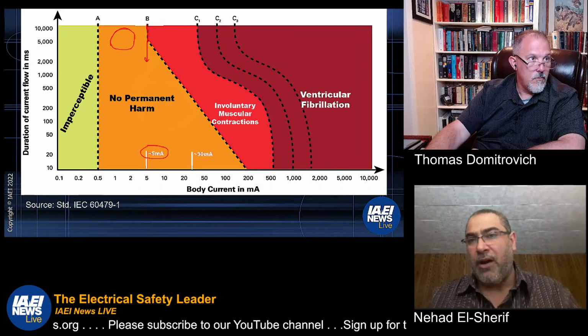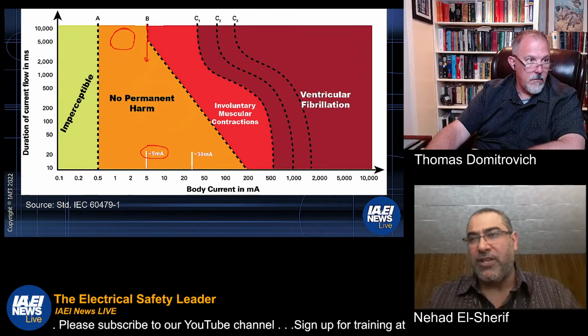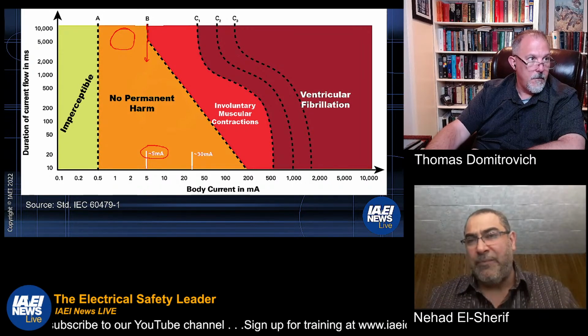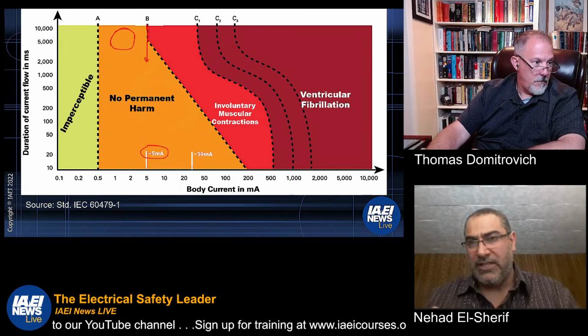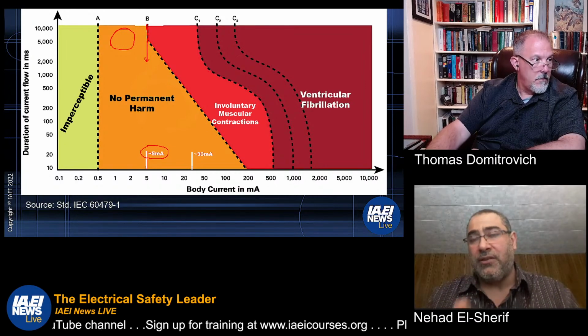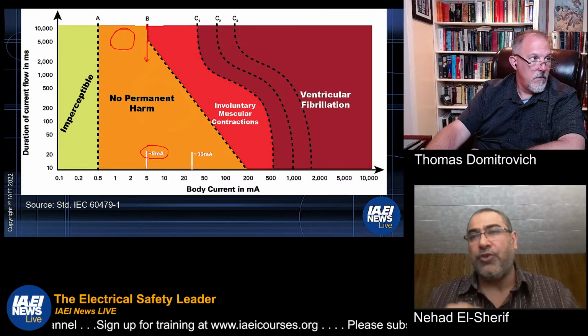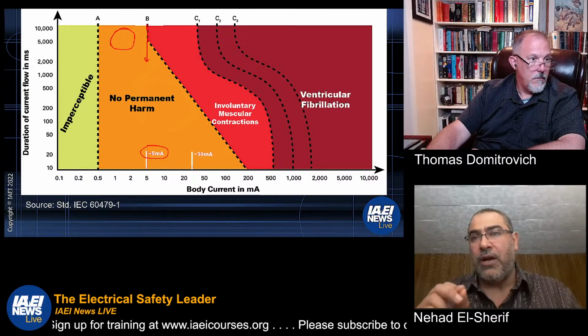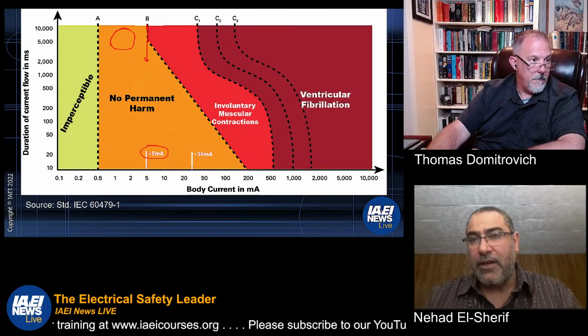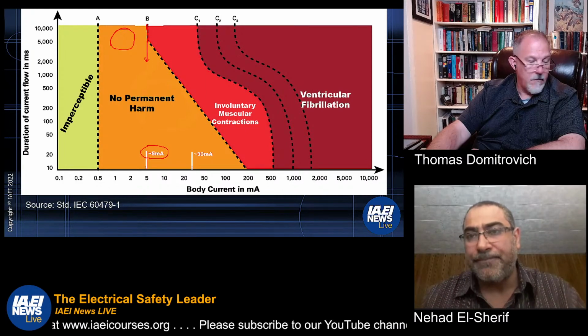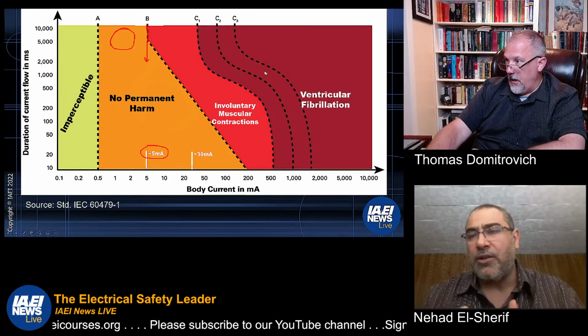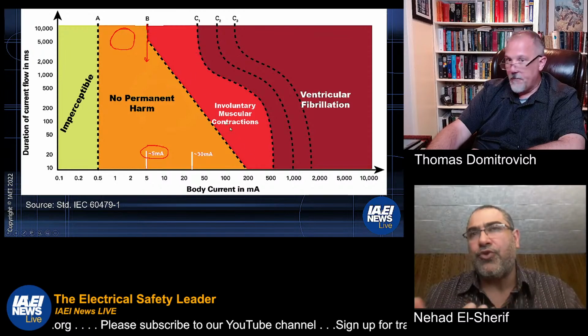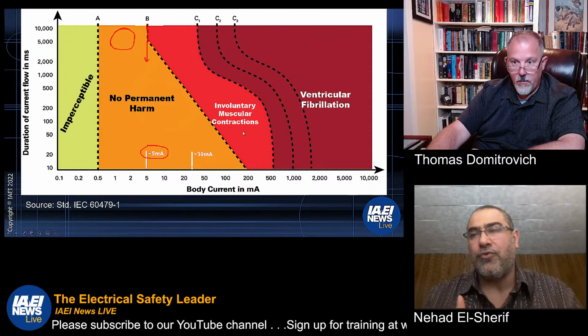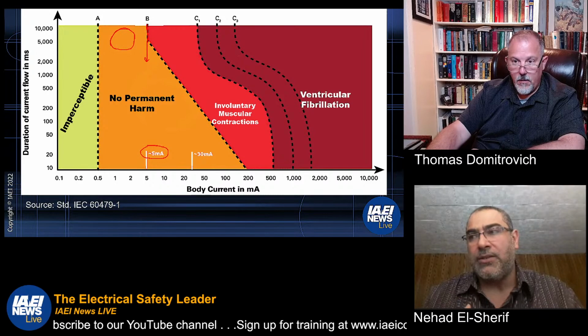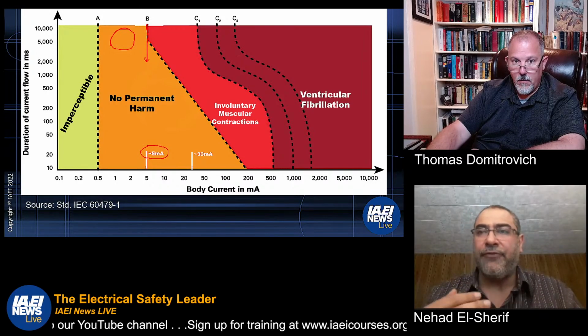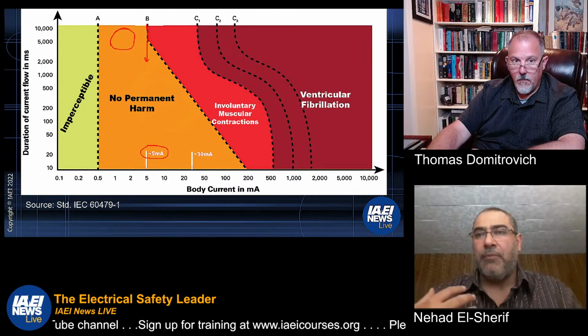But if you move higher up, and this is where it gets interesting with the special purpose GFCIs, up to 20 milliamps or 30 milliamps in this area, then time becomes really crucial. Because if you don't trip quickly enough, then you can get into the red zone, which is muscle contraction. You lose control over your muscles. You won't be able to let go anymore, because the amount of current is high enough to prevent muscle control.